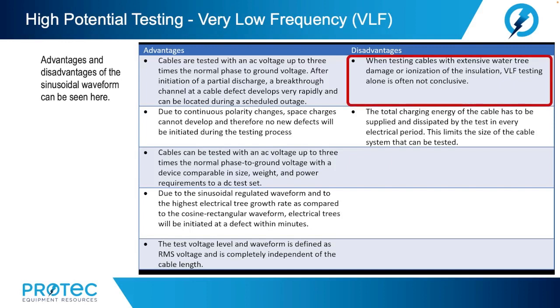When testing cables with excessive water tree damage or ionization of the insulation, VLF testing alone is often not conclusive. And the total charging energy of the cable has to be supplied and dissipated by the test in every electrical period. This limits the size of the cable system that can be tested.